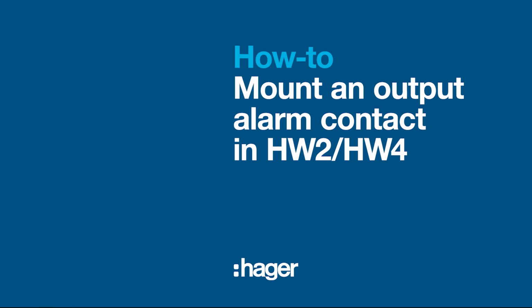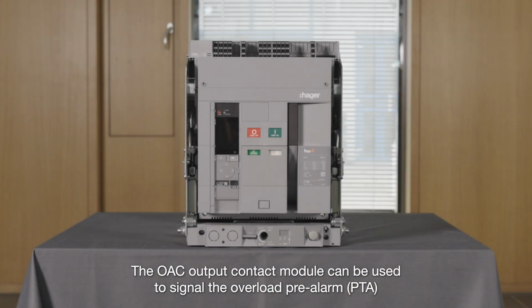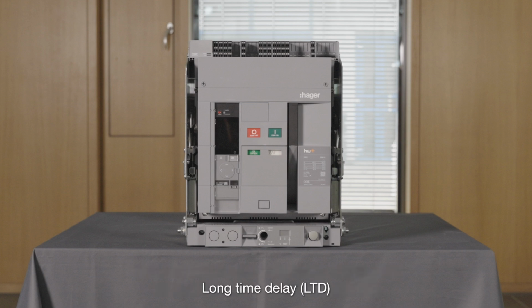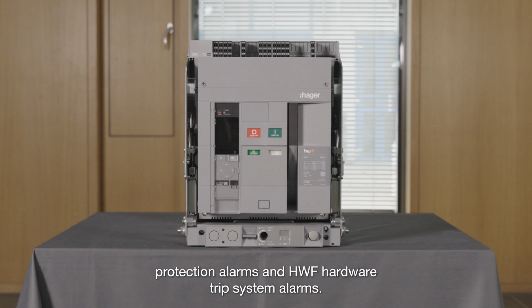The OAC output contact module can be used to signal the overload pre-alarm (PTA), long time delay (LTD), short time delay (STD), instantaneous (INST), and ground fault (GF) protection alarms, and HWF hardware trip system alarms.